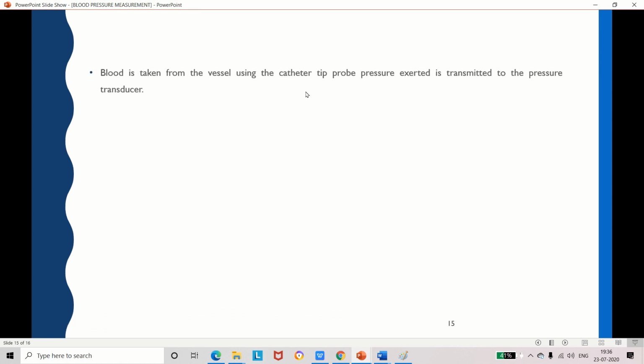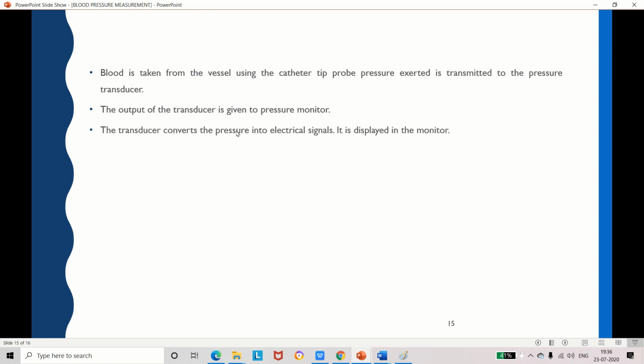Let us discuss all the points once again. Here we are using a catheter tip probe which we insert, and we are also using a pressure transducer. This transducer will convert the measured pressure into an electrical signal, it will be amplified, and it will be displayed on the monitor.